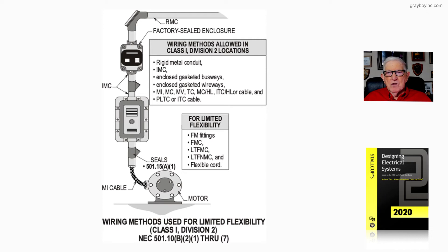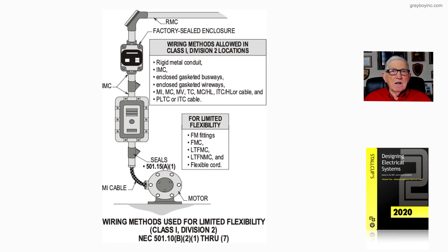— notice rigid metal conduit, IMC, enclosed gasket busways under certain conditions, and enclosed gasket wireways.